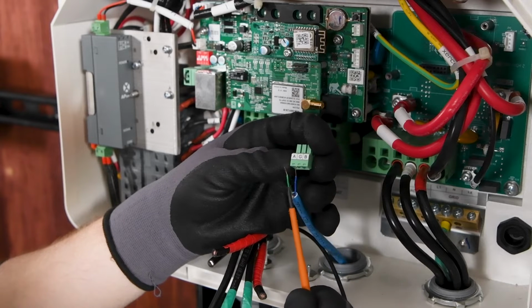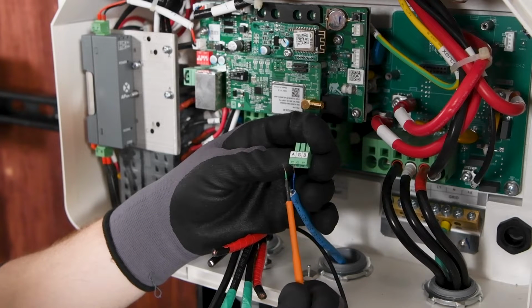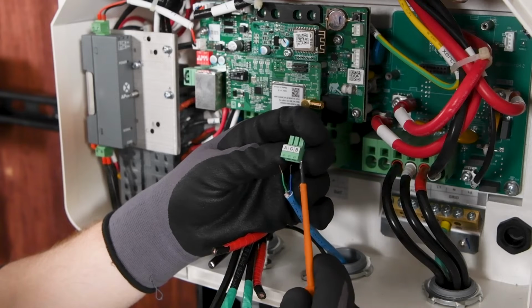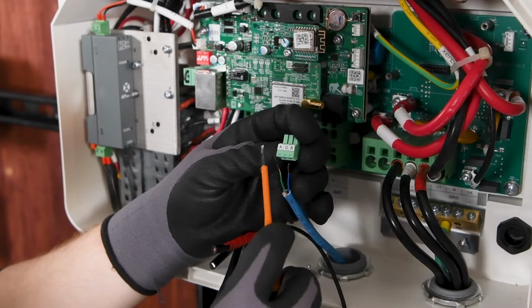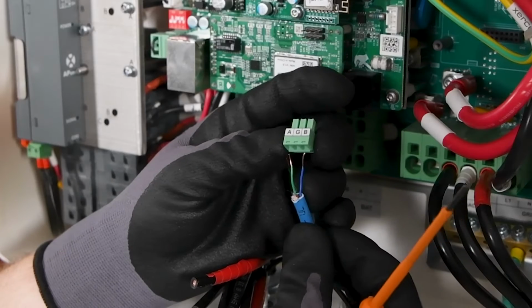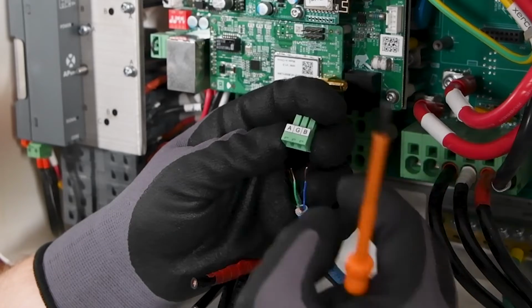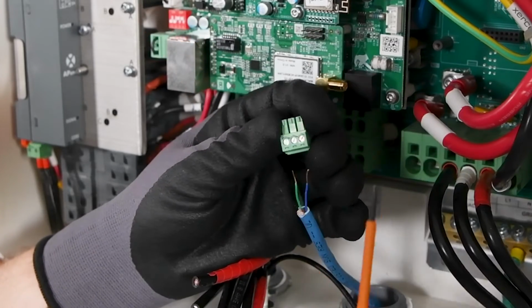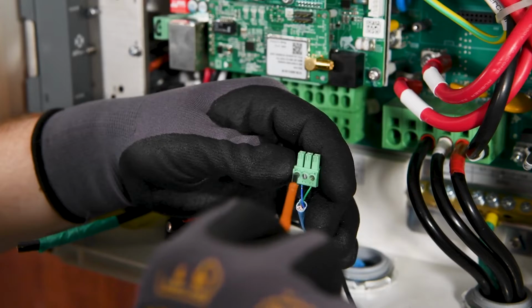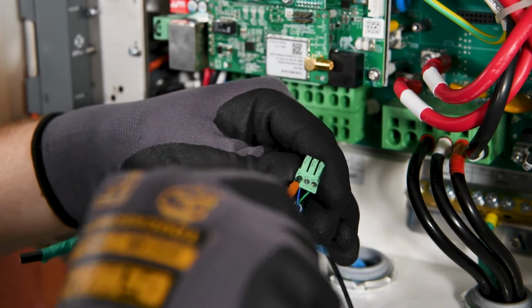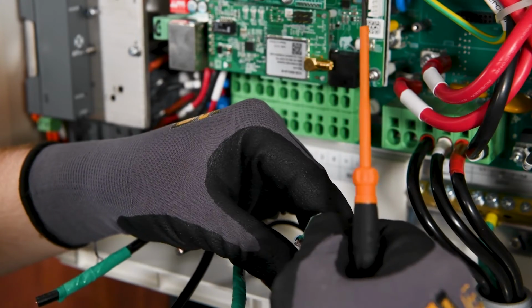What we'll do here is we'll take our Cat5 or Cat6 cable. We have our blue and our green conductors. Our blue will go to B and our green will go to A. To connect the communication cables to the terminal block, we will use a small flathead screwdriver to secure our 2 communication cables.